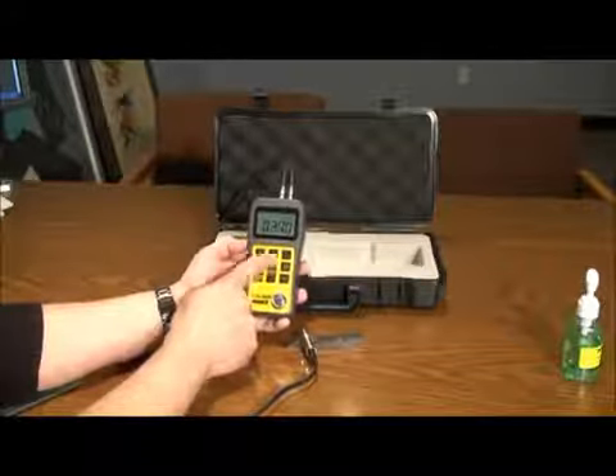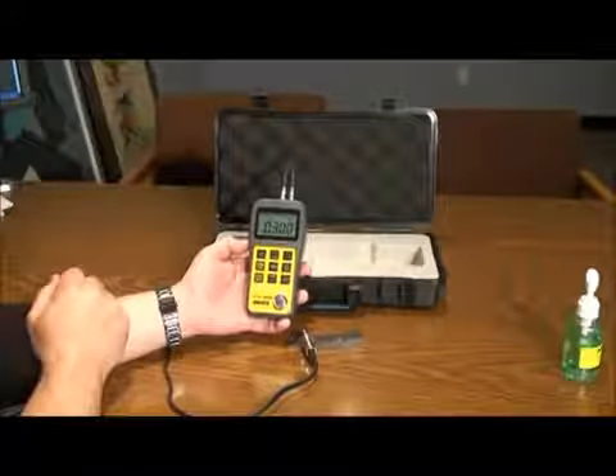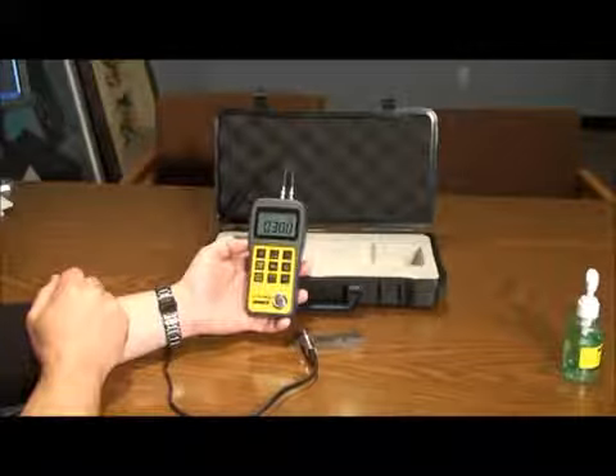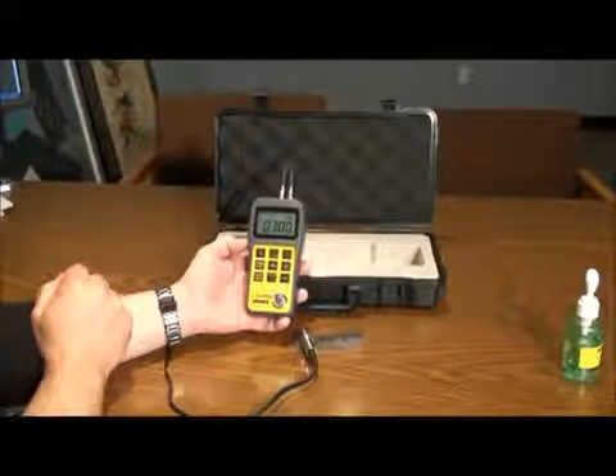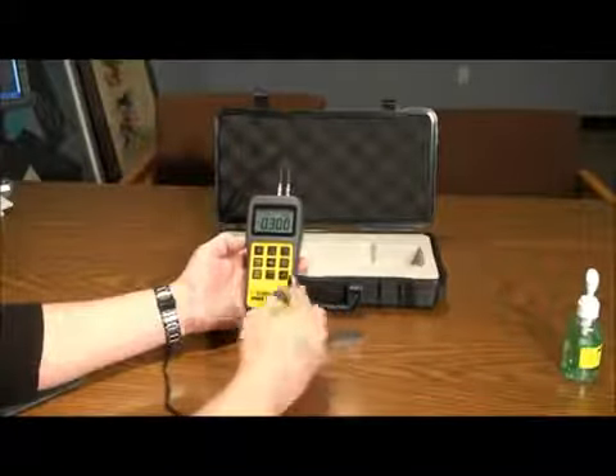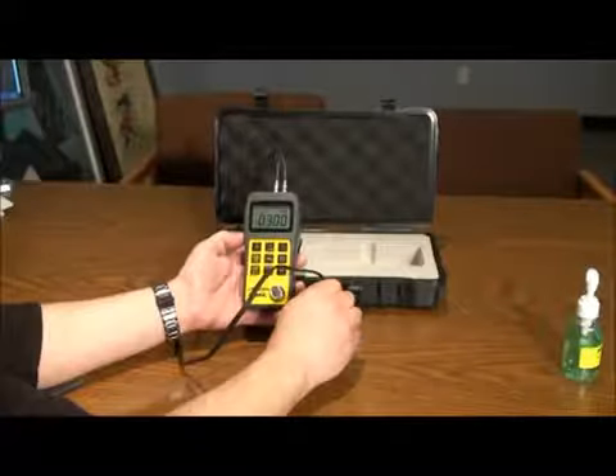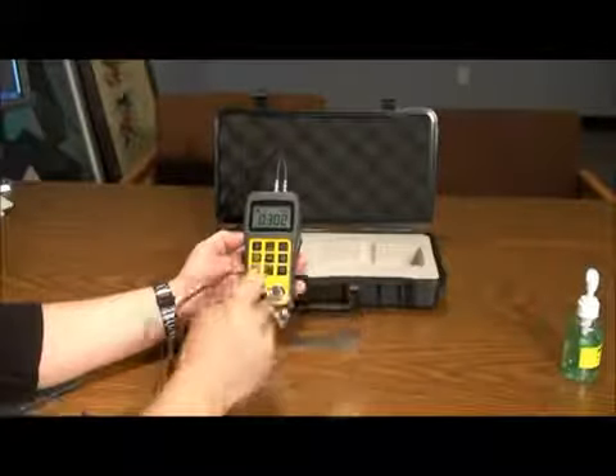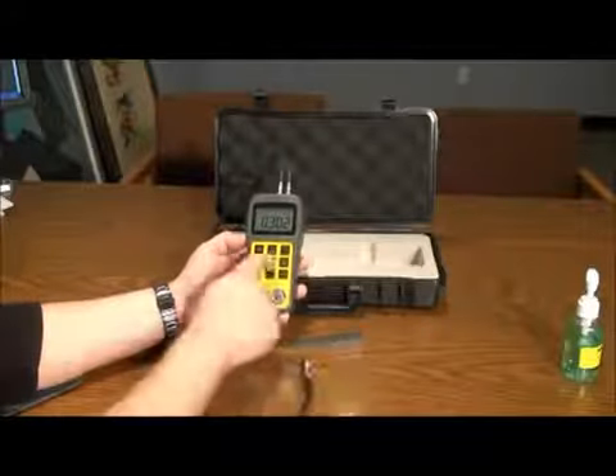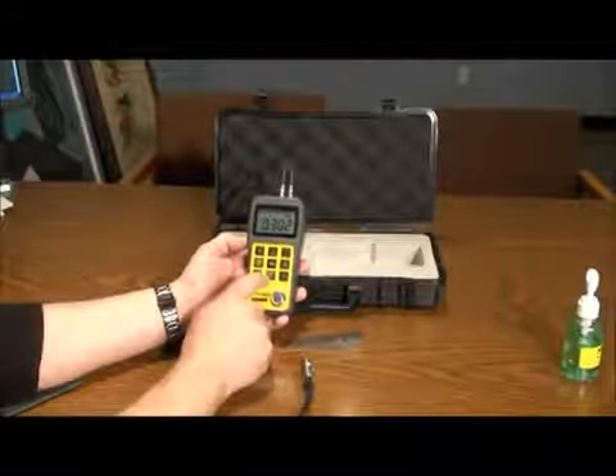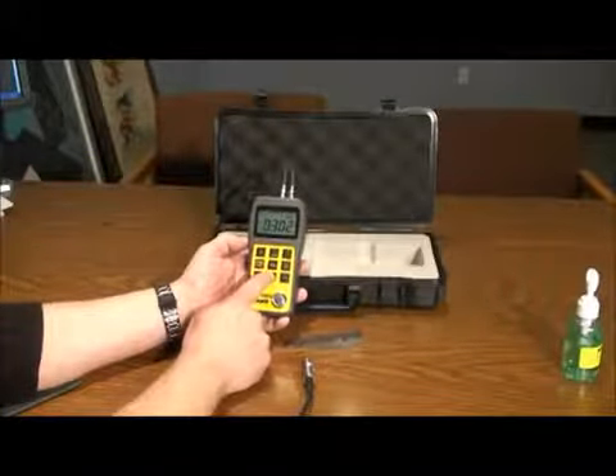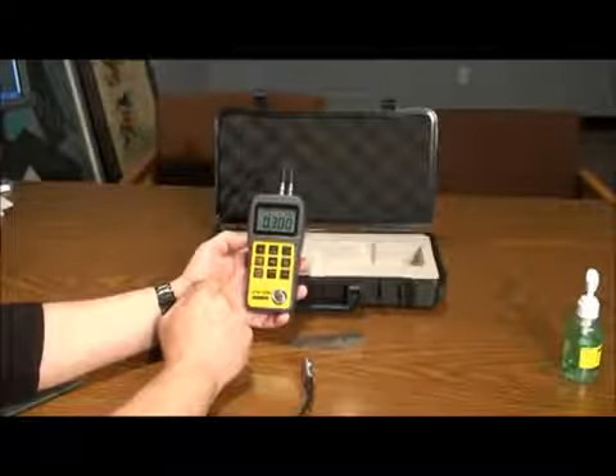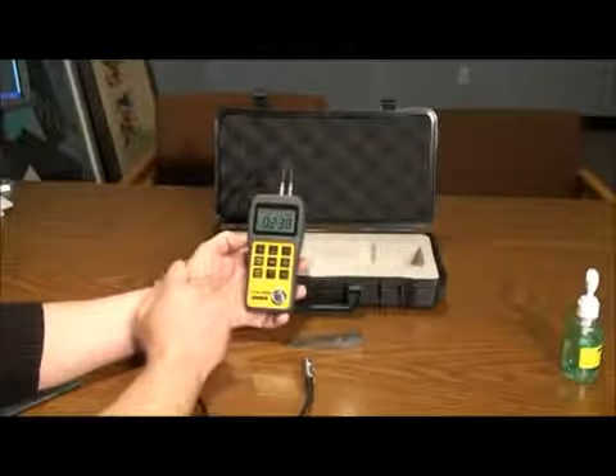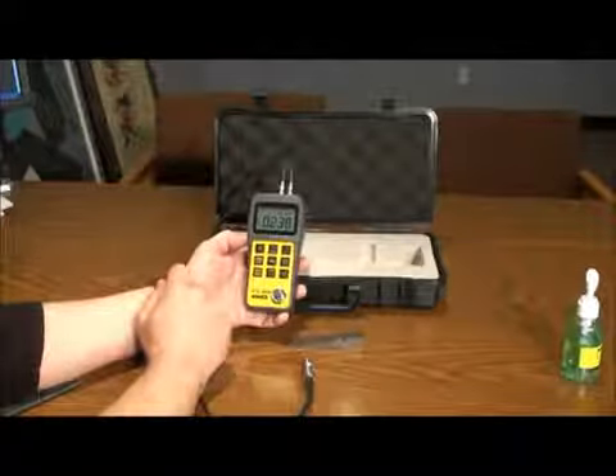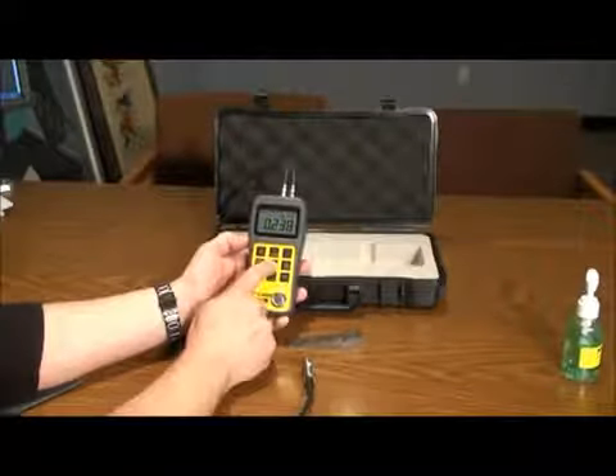There are velocity calibration methods to pinpoint the velocity of a material with a known thickness. Place the probe on a part with a known thickness, then remove the probe. Press the velocity key once. Adjust the value to match the known thickness of the material. Press the velocity key again and it will display the sound velocity for that material. Press the velocity button again to save.